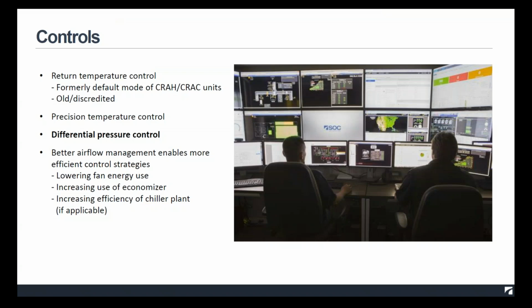Controls. One of the benefits you're going to achieve when you use hot aisle containment and an economizer is that you can expand the amount of time that you're on free cooling and reduce your fan energy. So somehow you have to control the fans to get to the appropriate speed. And I mentioned earlier, we use differential pressure control for that. In that strategy, we're trying to achieve a certain differential pressure set point where the hot aisle is slightly negative compared to the cold aisle. So if there is any bypass airflow, it's going from the cold aisle to the hot aisle and not creating hot spots, but you want it to be just slightly negative.